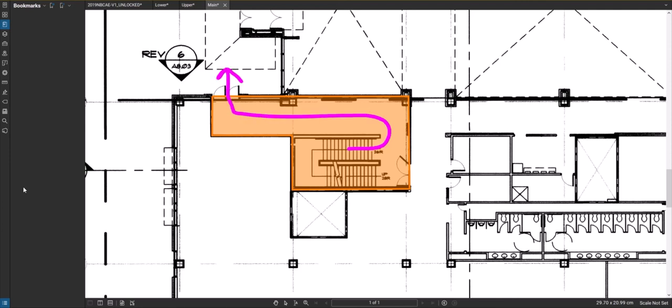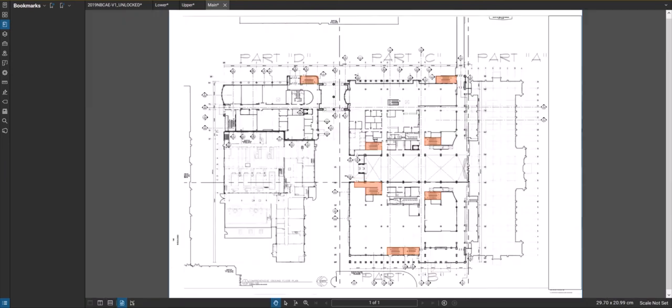In this case, the stair is not on the exterior of the building, so you can't just have a door from the stair to the exterior. So they increased the size of the stair, in a way, or added a corridor to the stair that shares the same fire separation. Now you're in that fire separation until you reach the exterior. That one's pretty straightforward, in understanding the idea of having to stay in the safety of the separation. Let's take a look at one of these other two stairs here.